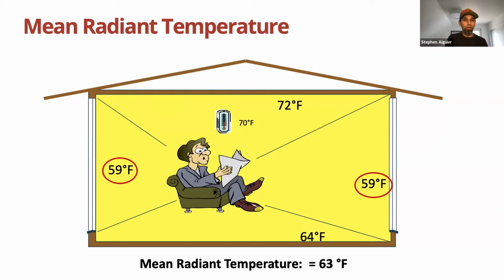You go through a freezer aisle though, maybe all the doors are closed, nothing's blowing out at you, but you're really cold all of a sudden. And that's because you're dumping your heat into those cold freezers at a much higher rate. And the mean radiant temperature just really plummeted. Air temperature is still 70 degrees, but mean radiant really dropped.